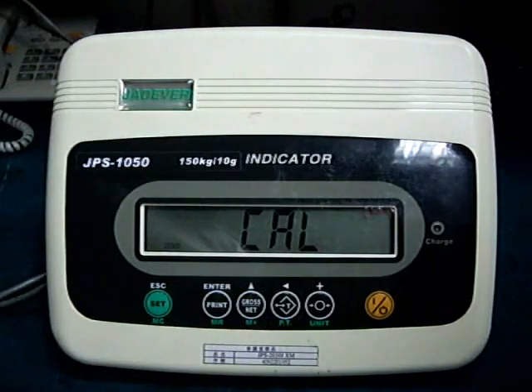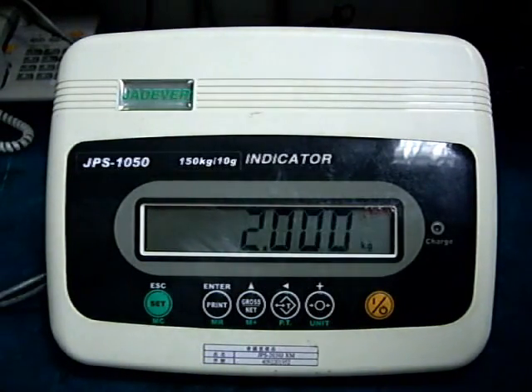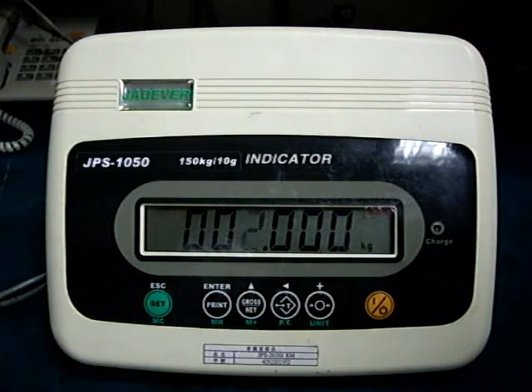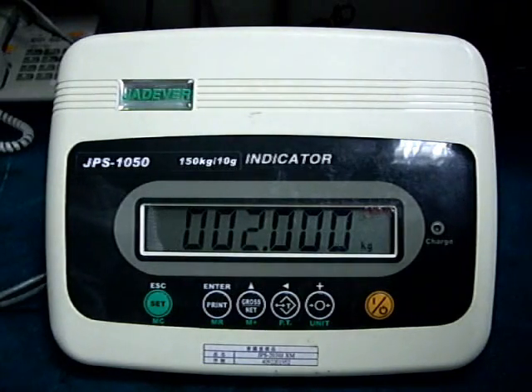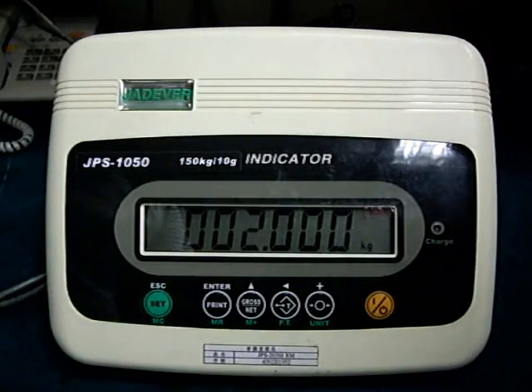The display will show 0 CAL, which indicates the zero point calibration is conducting. The beep will sound when zero point calibration has been completed. Then the display will show some digits. Please key in the weight value for span calibration.